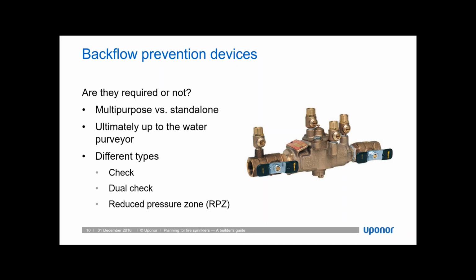And why is this such an important topic? You would say, well, let's just put it in and be done with it. Obviously, there's additional cost involved in every extra component, but it's important to note which type of backflow prevention device is being used. Some of the different types are going to be your single check, your dual check, or what's known as a reduced pressure zone valve. Sometimes these terms can be used interchangeably.